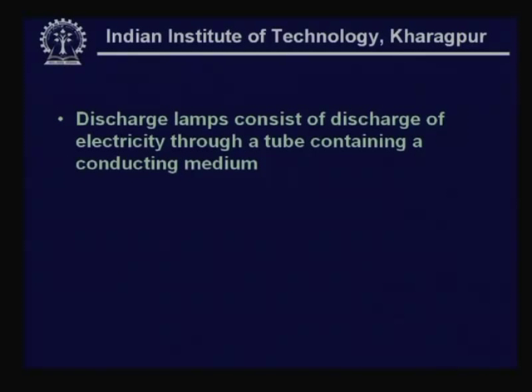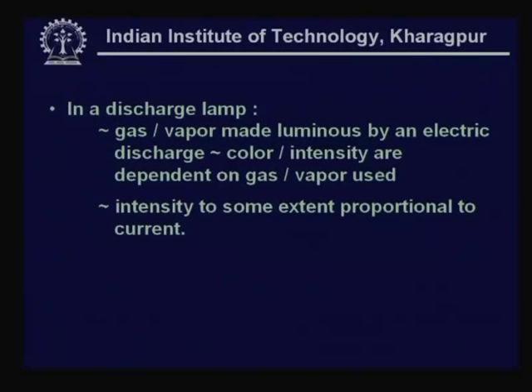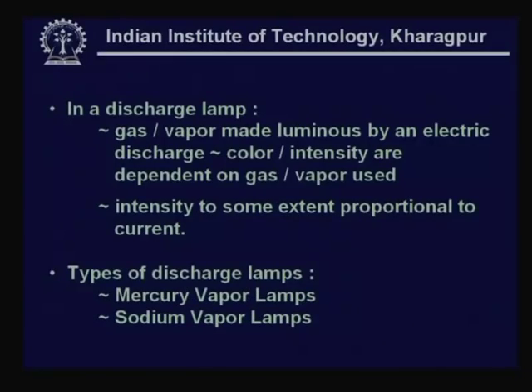Discharge lamps consist essentially of a discharge of electricity through a tube containing a conducting medium. Types depend on electron emission - this could be based on electric field causing field emission in a cold cathode type, or thermionic emission where a heated filament causes the cathode to emit electrons at higher temperature. In essence, a discharge lamp has a gas or vapour made luminous by electric discharge whose colour and intensity depend on the gas or vapour used, and intensity is proportional to current. The arc is a constant current phenomenon, therefore additional accessories are required.